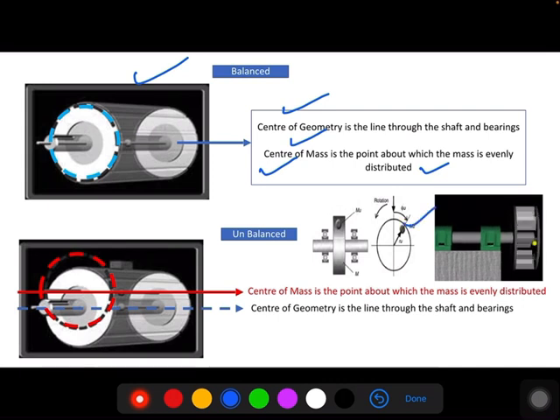If the equipment is unbalanced because of some uneven distribution of mass, then it creates the centrifugal force. Because of centrifugal force, this tries to pull the impeller to rotate off center, and what happens is this center of mass separates from the center of geometry. There is an offset between the two. This red circle clearly indicates the center of mass, and this at the bottom, this line clearly indicates the center of geometry. The center of geometry and center of mass, there is an offset. Because of this offset, it gives undue forces on the bearing and plummer block. So generally we call it as eccentricity. There is an eccentricity because of unbalance.